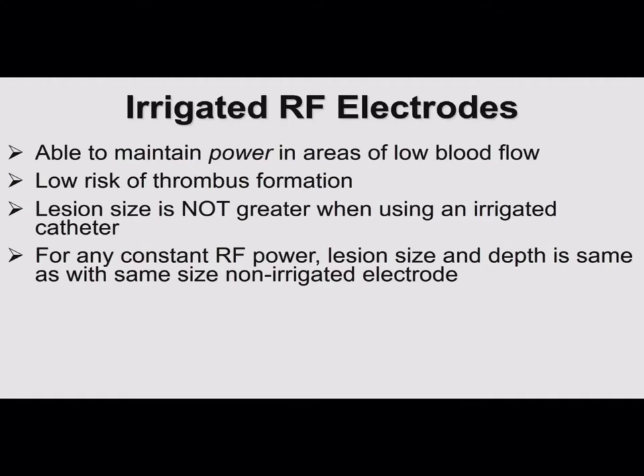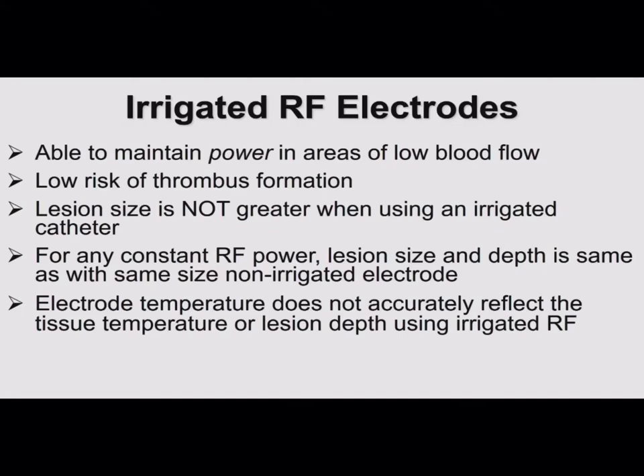Maybe you can stay on longer with irrigation because you're not heating the tip and getting char, but for the same duration and power, you're getting the same lesion size. On the other hand, if you're delivering 10 watts but your temperature is shooting up to 70 degrees with a non-irrigated catheter, that's when switching to irrigated ablation will help — you can cool the tip and deliver more power where you were temperature-limited before. The one thing you lose with irrigated ablation is that temperature from the thermistor is no longer a surrogate of lesion size because you're cooling the tip. Temperature then is just a safety marker — if it's shooting up, something's wrong, like plugged holes or disconnected tubing.